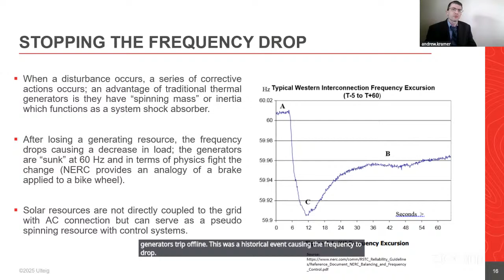Solar resources are not directly coupled to the grid. They don't have a direct AC coupling to the grid. They connect through an inverter, but there are control mechanisms you can use to approximate a pseudo mass from them. I'm not going to have time to talk about that here, but I want to make sure we don't talk down renewables and make it sound like they don't have any implication at all. And what you can see here on the right is a typical disturbance event. This is an example from WECC. You have the grid operating right around 60 hertz, and then a few generators trip offline. This was a historical event causing the frequency to drop. And we'll actually go through what happens here to bring the frequency back up as we click along.